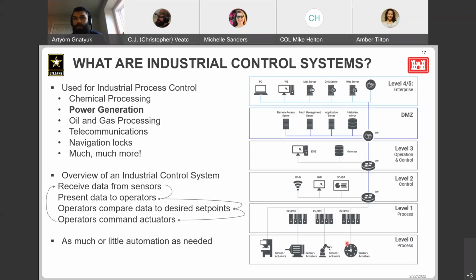So we grab this data, it goes up to the PLC or RTU, kind of in the level 1 realm, and then we present this data to the operator. We're grabbing electrical signals—maybe a negative 10 to 10 volt signal, or a 0 to 20 milliamp signal, a 4 to 20 milliamp signal—and we convert that into something that makes sense to the operator.